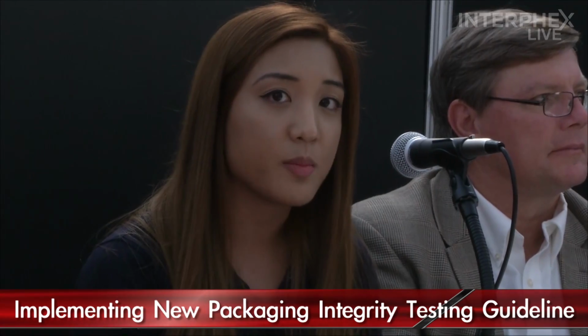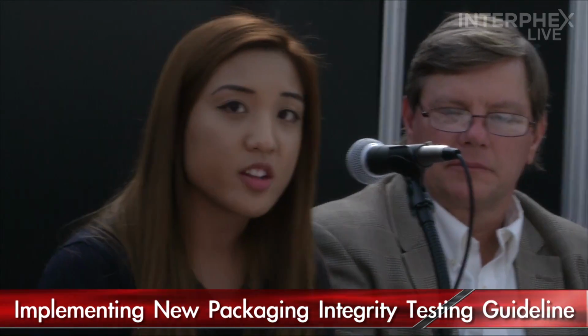Your second set of controls are your positive controls, and these are packages with an intentionally made defect. So for example, there are laser drill defects. These defects are created in the actual component material of your sample. So if you have a vial, you would want to create the laser drill defect in the vial wall. And these laser drill defects can be created to a certain micron size: 2, 5, 10 microns. You want to create laser drill defects or any defects in a range of sizes to build in that linearity of your method. It's very similar to any analytical method. I think that's what we really want to stress: CCI is not an art form, it's a science. It's an analytical method that needs to be developed and optimized.